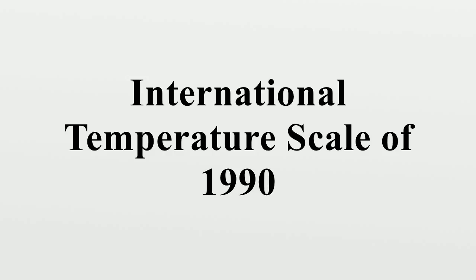Although "International Temperature Scale of 1990" has the word "scale" in its title, this is a misnomer that can be misleading. ITS-90 is not a scale; it is an equipment calibration standard. Temperatures measured with equipment calibrated per ITS-90 may be expressed using any temperature scale such as Celsius, Kelvin, Fahrenheit, or Rankine. For example, a temperature can be measured using equipment calibrated to the Kelvin-based ITS-90 standard, and that value may then be converted to and expressed as a value on the Fahrenheit scale.